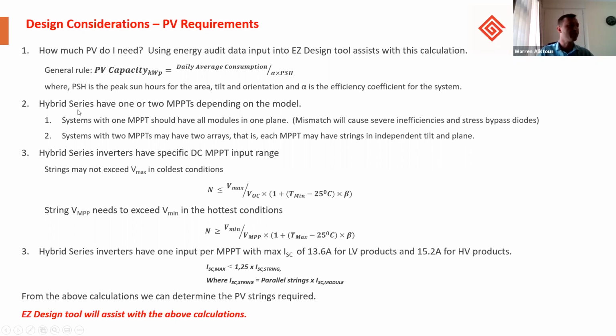So hybrid series inverters have either 1 or 2 MPPTs depending on the model. Systems with 1 MPPT should have all modules in one plane. What does that mean? All the modules need to be on a single roof structure facing the same way at the same tilt. If you do not do this, you'll have mismatch, and mismatch causes severe inefficiencies and stresses bypass diodes. Systems with 2 MPPTs may have 2 arrays, each array having its own tilt and orientation, and again, should not have any mismatch in the same string, which will cause inefficiencies and stress bypass diodes.